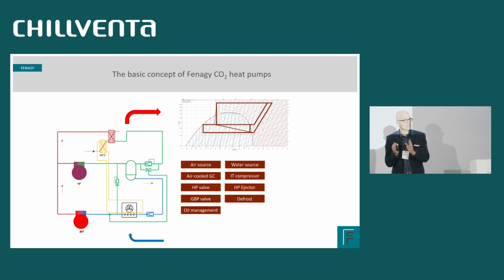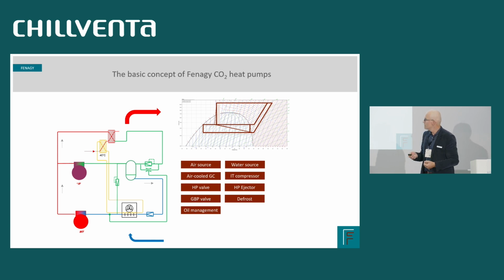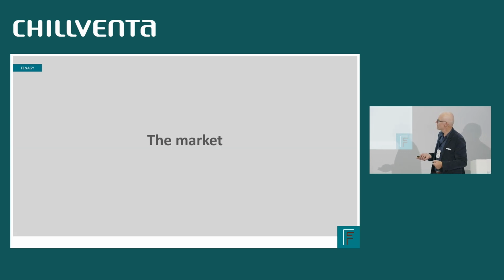So the heat pump is not stopped. It produces heat, but at a little bit reduced level. That is a demand in a real heat pump. It's not like a household or residential heat pump where it's stopped and it takes the heat from the house. This is not the way we can do it in district heating. I hope you get my point. It's a pretty simple piece of equipment, actually.